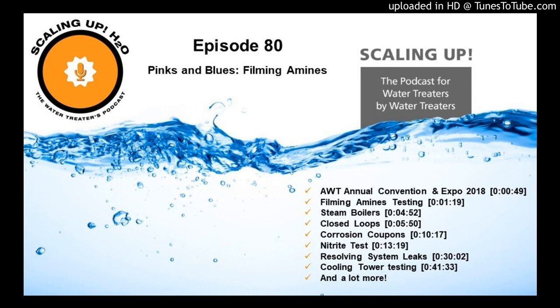Well, closed loops, folks, we have solved how to treat closed loops many years ago. And when we add a metal like aluminum to it, well, now it's not playing by the rules. And what I mean by that is most of us are using something like a nitrite-based program in a high pH buffered system. So we probably have a pH of 8.5, probably all the way up to 9.9, somewhere around that area. And we do that because the higher the pH in that environment, we actually can inhibit the corrosion going on in the mild steel.